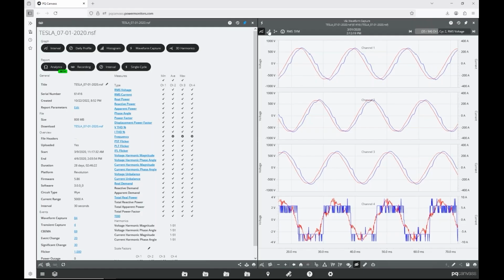And the current distortion actually gets worse as the current lowers. So as the battery starts to taper, the distortion on the current will become worse and worse, but the current itself is dropping. So in an absolute sense, it doesn't matter as much. There'll be some intermediate point, usually around 60 or 70% of full output, where it's the worst on the voltage.